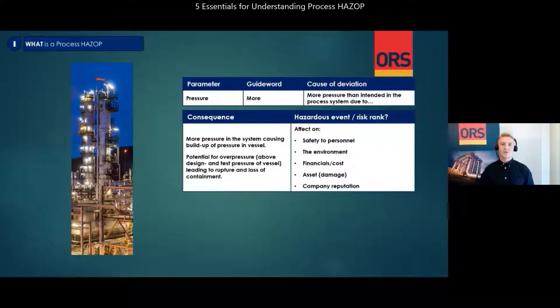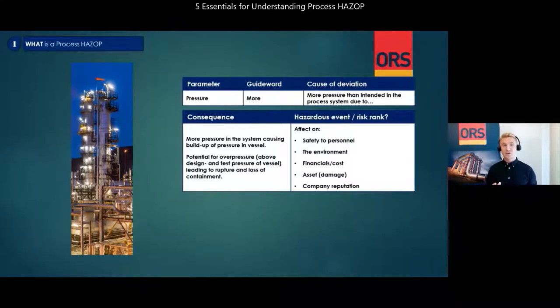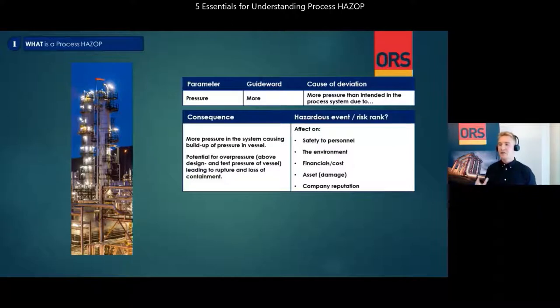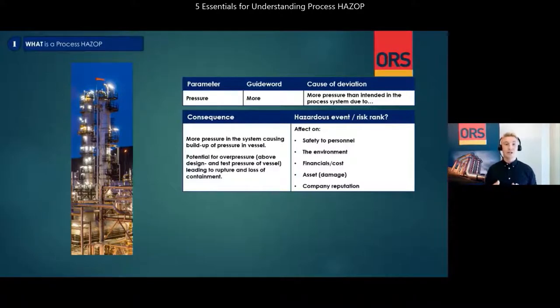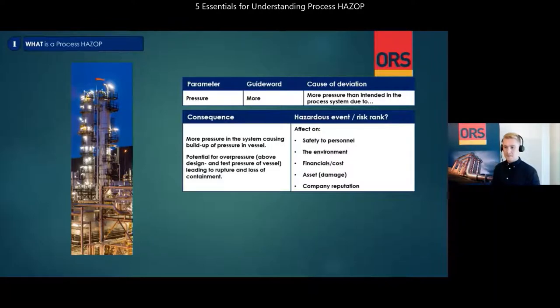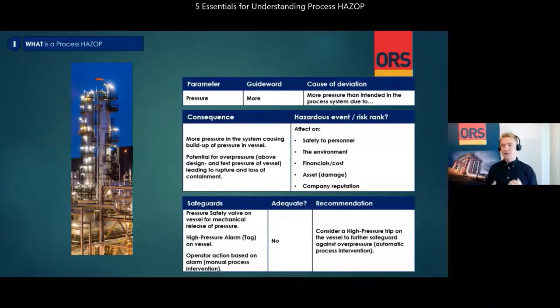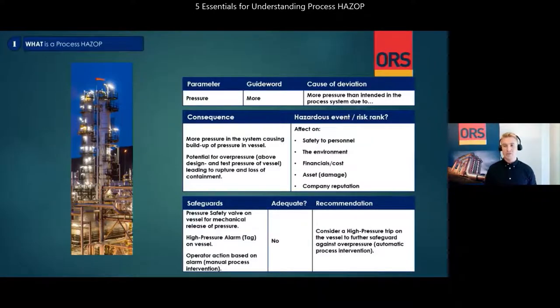Based on the client's requirement, a risk ranking may be applied to assess if the risk is acceptable or not. The consequence is normally described and risk ranked in the case of the following being affected: safety to personnel, the environment, financial and cost, asset damage, and company reputation. After the consequence is established, the group identifies and lists all safeguards that are in place to either prevent the hazardous scenario or mitigate the consequence. Such safeguards may be a pressure safety valve on the vessel, a high pressure alarm on vessel, and operator action based on the alarm, which is a manual process intervention.